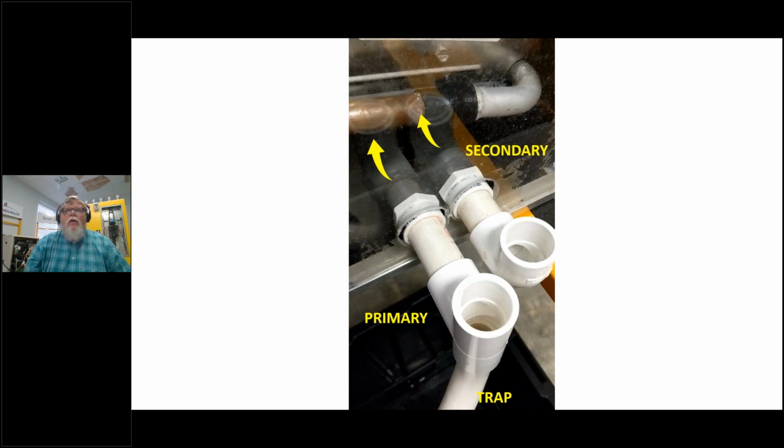Now, on an average day, it might not run over. It might not produce enough condensate. When the unit shuts off, it releases the negative pressure. The pan drains itself. But on a really hot, scorching day with real high humidity, it would probably run over. And then, it could cause a flood. And the installation is the problem.